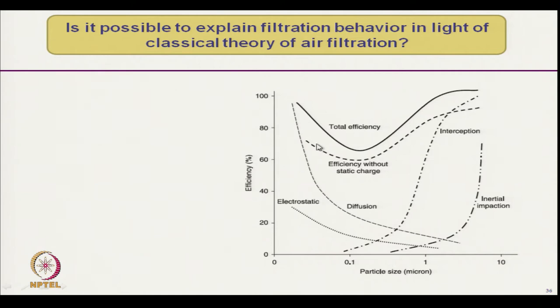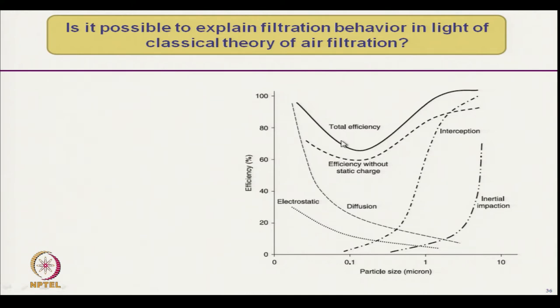As particle size increases, diffusion contribution reduces. But after a certain particle size, efficiency again increases due to inertial impaction and interception. This is the typical shape of the combined efficiency curve. Using electrostatic charge gives slightly higher filtration efficiency, but the typical shape of the curve remains the same.